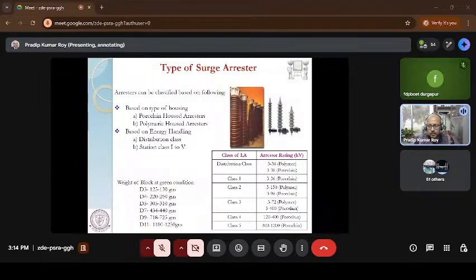Now, if you look at the classification of the surge arrestor, there are two major classifications based on housing. One is insulator based, and the second is rubber based, which is basically polymer. Mostly in polymer based, the products are in a small range, small rating, hardly around 72 to 100 kV surge arrestors are available. But in porcelain based surge arrestors, it can go up to 1200 kV also. Earlier it was 400 to 800. Now people are talking about a 1200 kV surge arrestor because we have developed a 1200 kV transformer. So to protect that 1200 kV transformer, we need a 1200 kV surge arrestor as well.